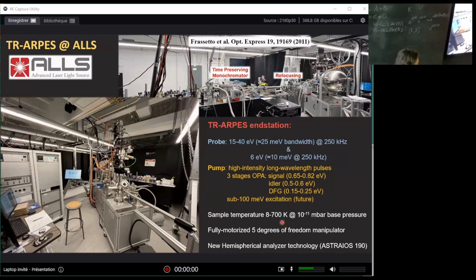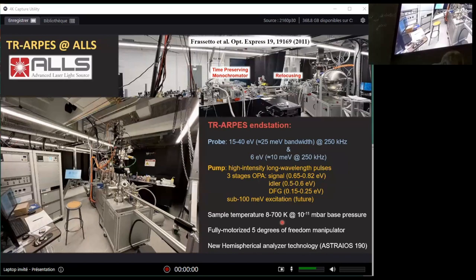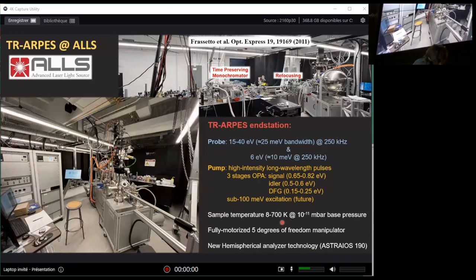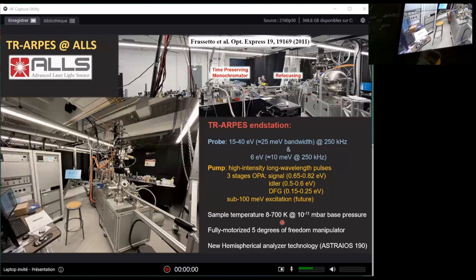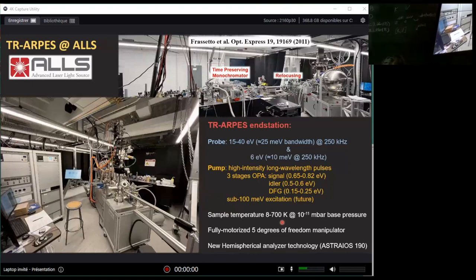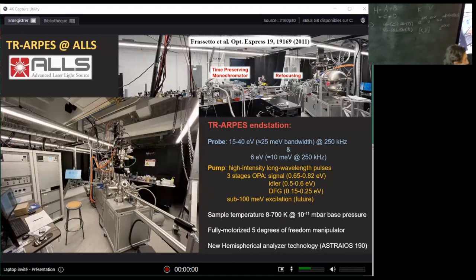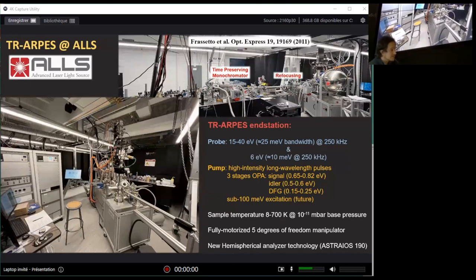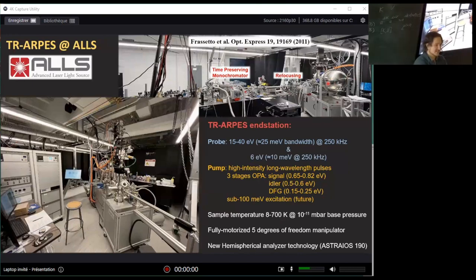A few words about the system. This is a state-of-the-art ARPES system. We have a closed cycle cryostat. We can measure from below 10K, let's say 8K on the sample, up to potentially 700K, all at the 10^-11 millibar scale. It's a fully motorized manipulator, but I would say the key feature of this system is the new hemispherical analyzer, the Astraios 190 by Specs, which allows us to detect photoemitted electrons within a cone of emission of 60 degrees. Consider that previous deflector technology for hemispherical analyzers allowed a maximum acceptance angle of 30 degrees, so this is a factor of two better.